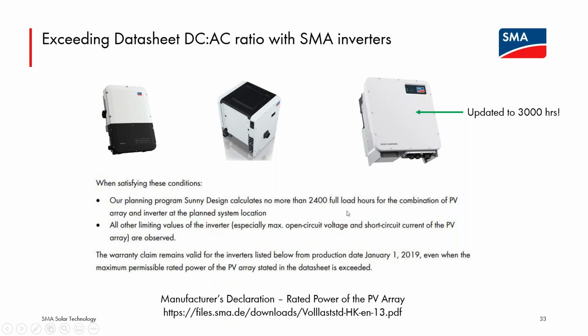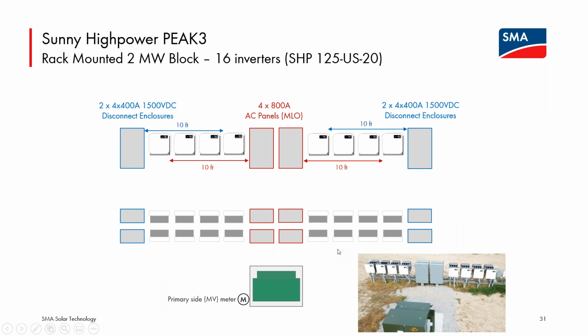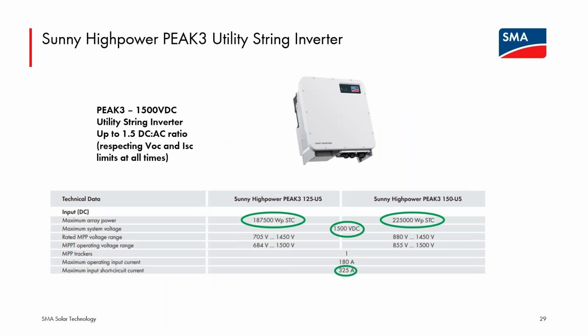Document the design and show that the full load hours are under the limit for the devices. And we see that very commonly for both the CORE1 and the PEAK3, that people want to do that. So definitely you won't be the first if you want to go past that 1.5 ratio.